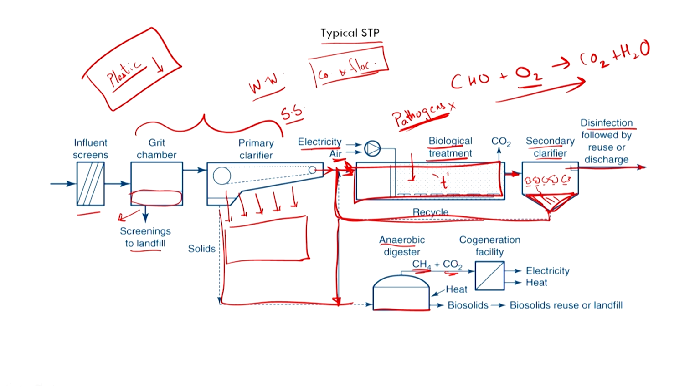So, the CH4 can be used for generating electricity. But the key issue here is that for energy recovery from an anaerobic digester to be efficient, you need plants to be at least 50 MLD, million liters per day. If it is less than that, I came to know that the energy recovery devices which can generate electricity are not very efficient at low loadings, let us say. So, if any entrepreneur wants to look into it, this is one aspect to keep in mind.